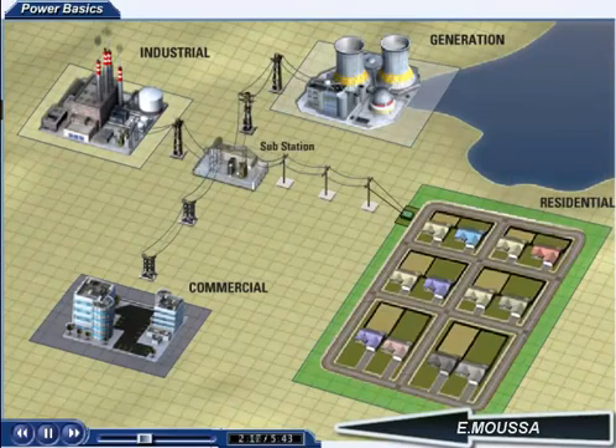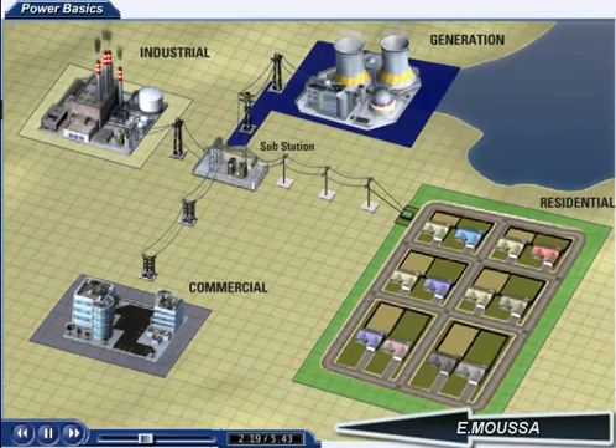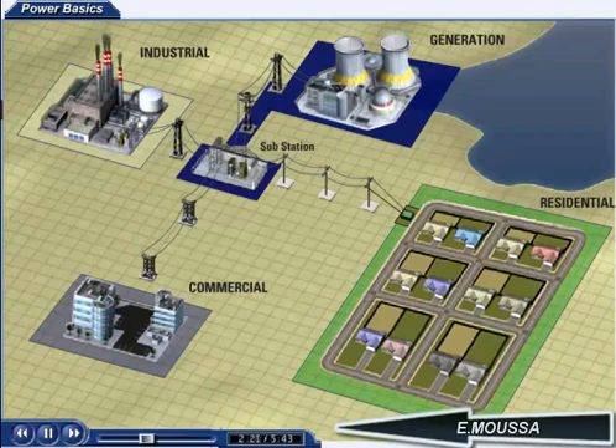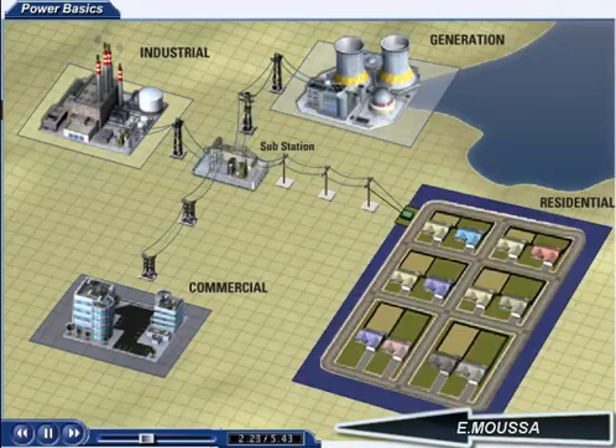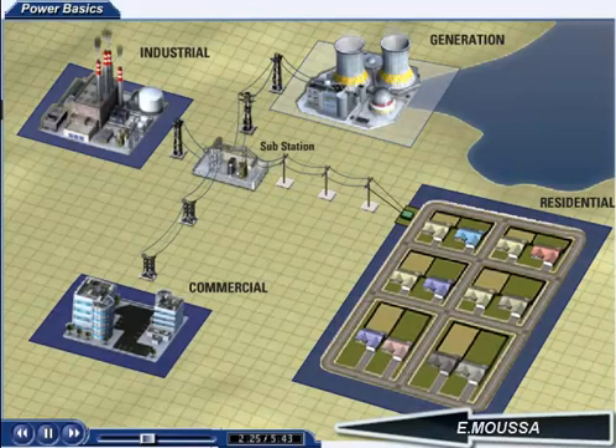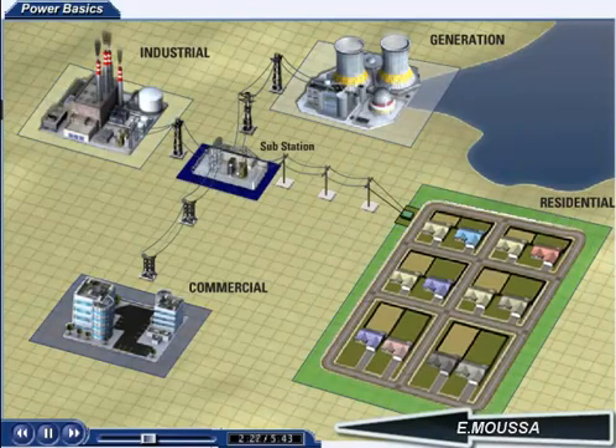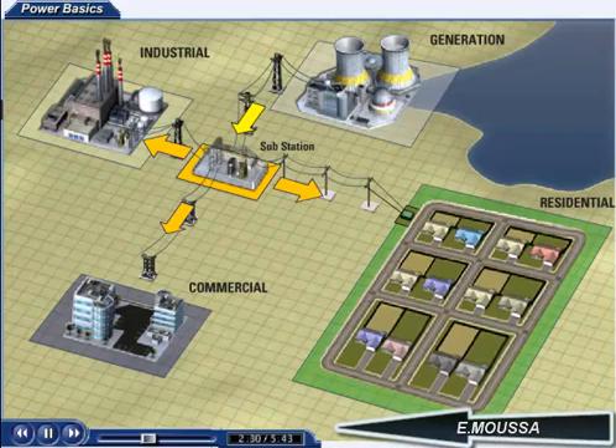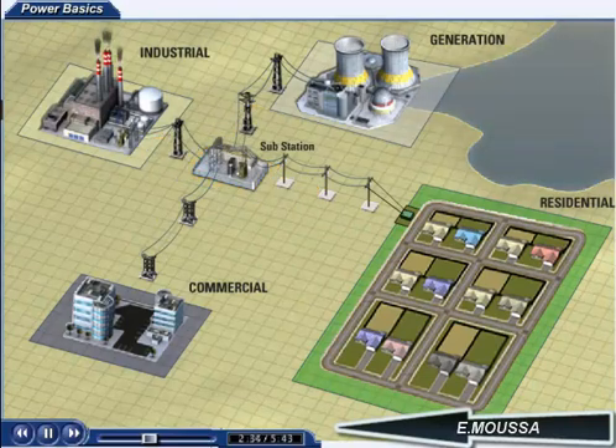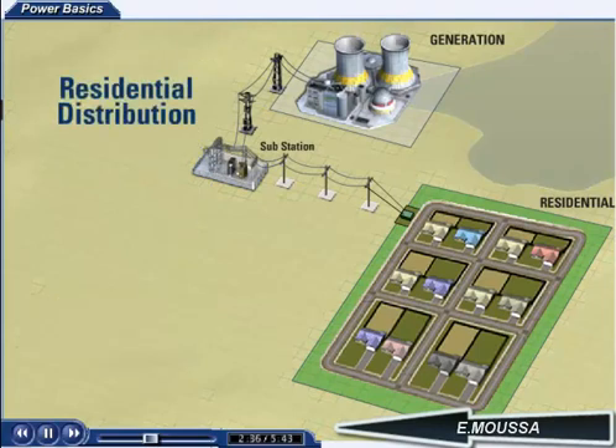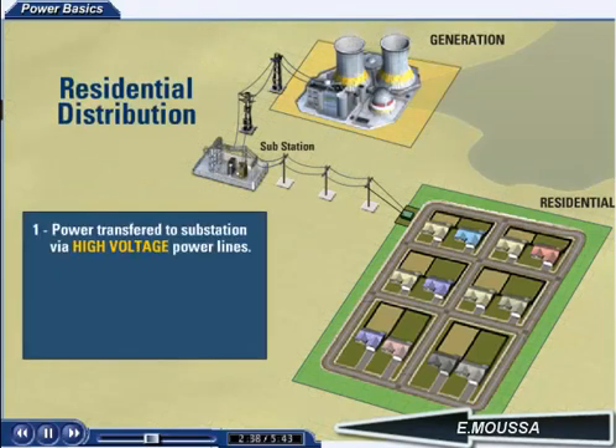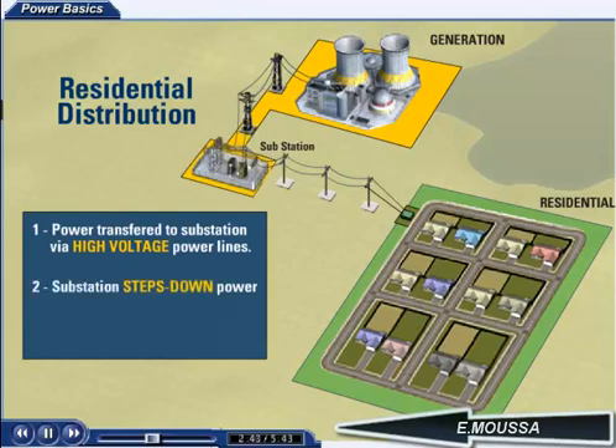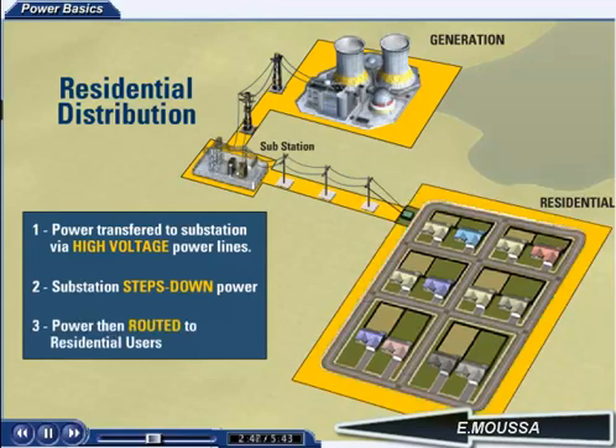The three-phase power travels from the generating station over high power lines to substations. Different voltages are required for residential, commercial, and industrial customers. And so, at substations, breakers and transformers route and step down the voltage to a suitable level for distribution. Let's take a look at a typical distribution system for a residential customer. Let's recap. The generated power is transmitted via high-power transmission lines to a substation, where it is stepped down and routed to residential users.